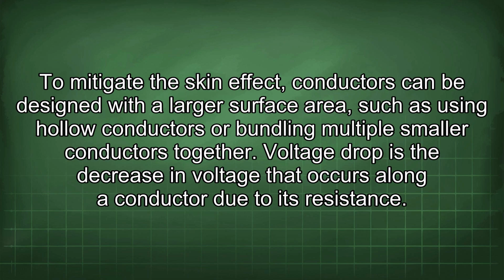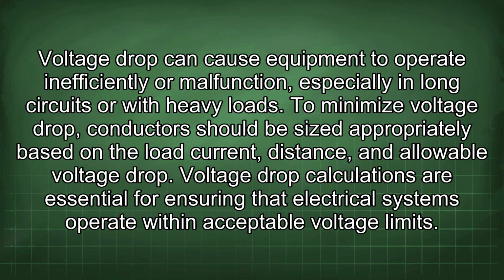Voltage drop is a decrease in voltage that occurs along a conductor due to its resistance. Voltage drop can cause equipment to operate inefficiently or malfunction, especially in long circuits or with heavy loads. To minimize voltage drop, conductors should be sized appropriately based on the load current, distance, and allowable voltage drop. Voltage drop calculations are essential for ensuring that electrical systems operate within acceptable voltage limits.